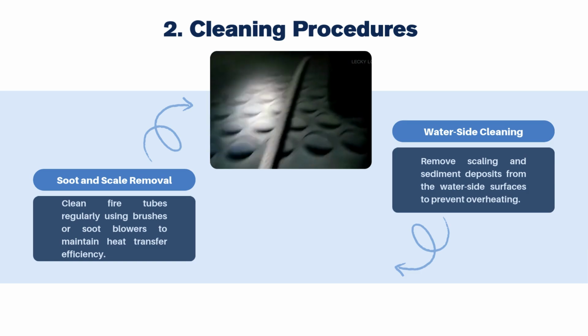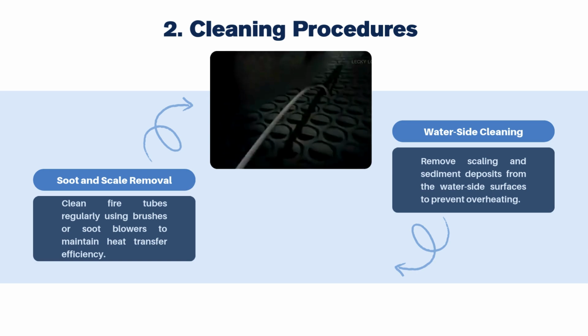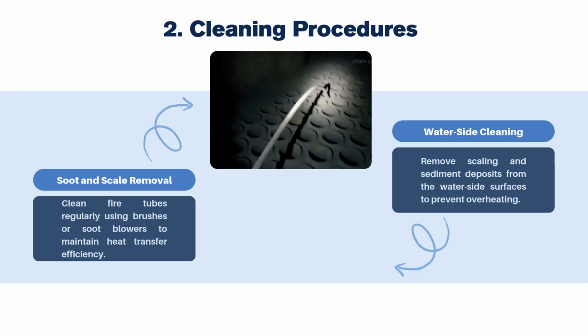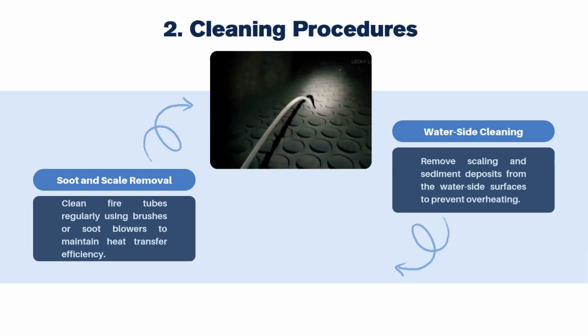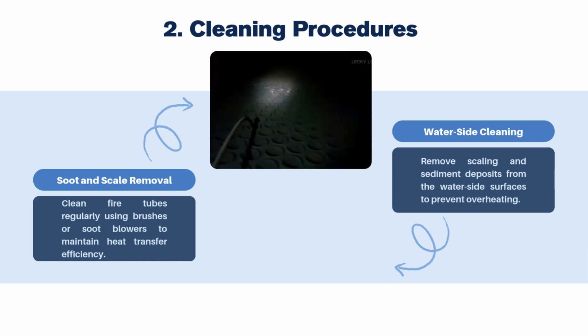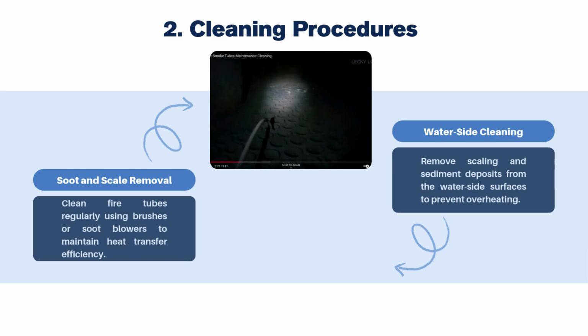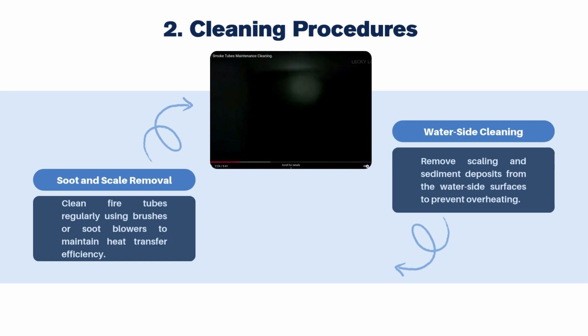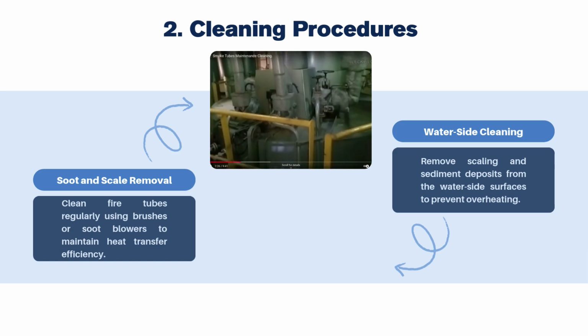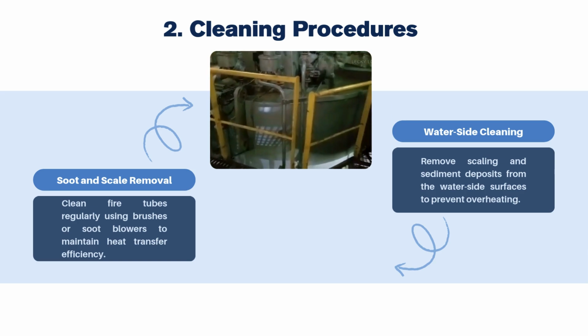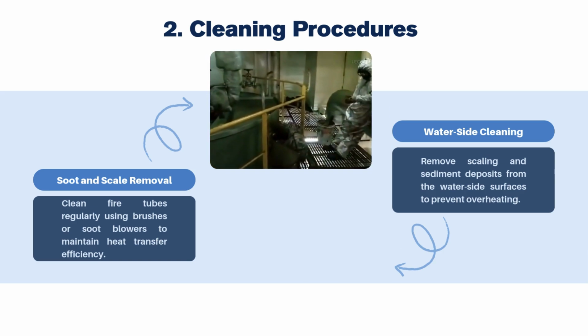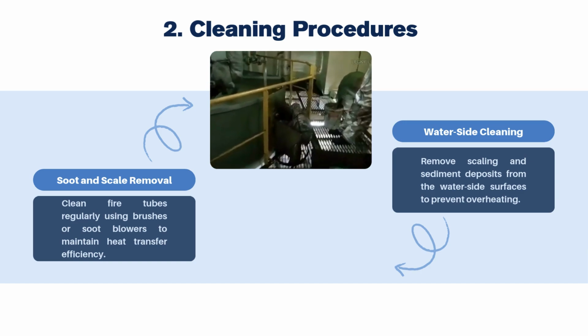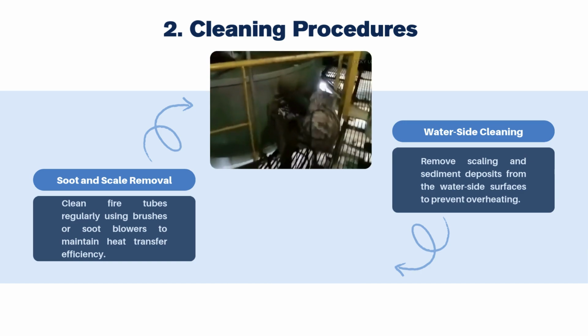To clean the soot deposits. We will do this as routine maintenance only. But before you start the cleaning of a smoke tube, make sure that the boiler oil burner is stopped and remain in stop mode. And of course, the main engine is not running. You should also allow the boiler to cool down before you open the manhole. And the most important thing, safety first. Wear proper PPE like disposable coverall, eye goggles, gloves, and never work alone.